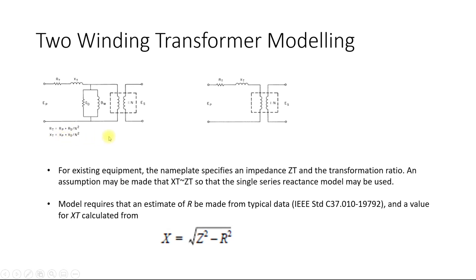Normally, we do not consider the conductance and magnetization current values because they are very small, so we can neglect the no-load magnetization current and conduction losses. If we neglect these iron losses and the magnetization current, we are left with simply Rt and Xt. From a transformer, we only need the values of resistance and reactance — R provides the transformer real losses while Xt provides the transformer reactive losses.